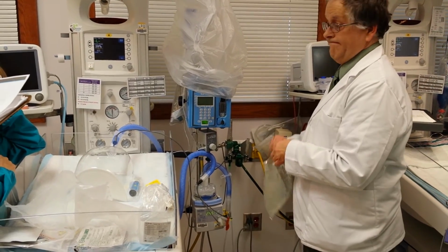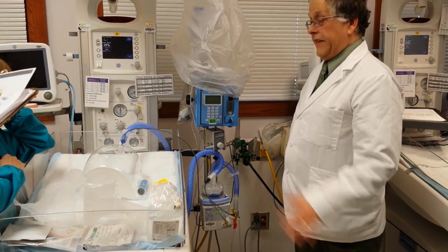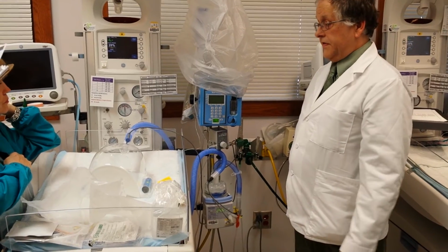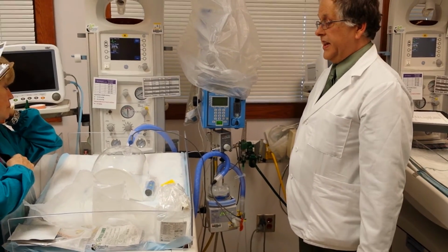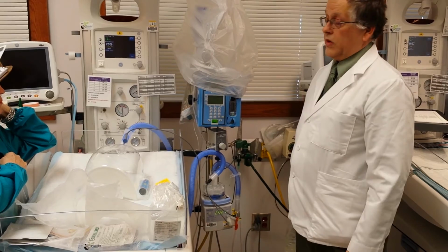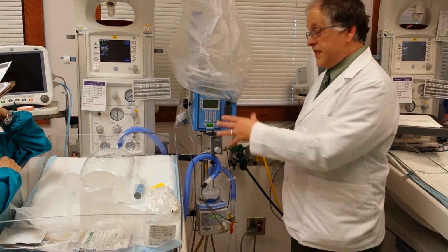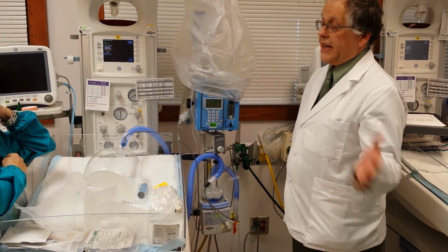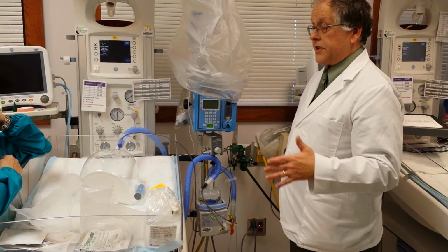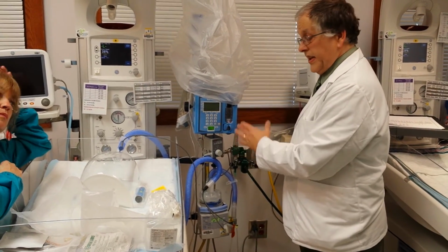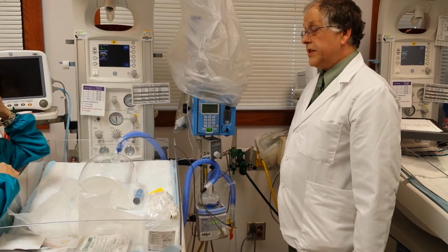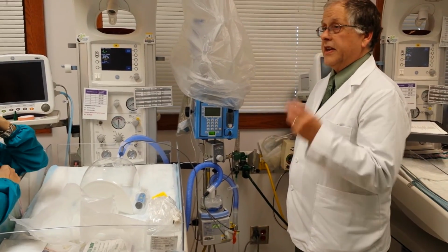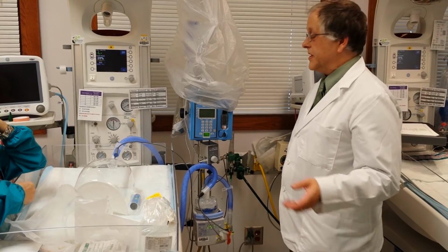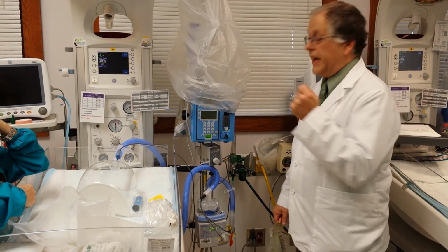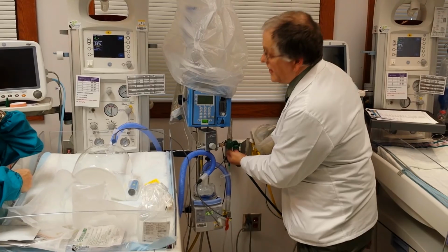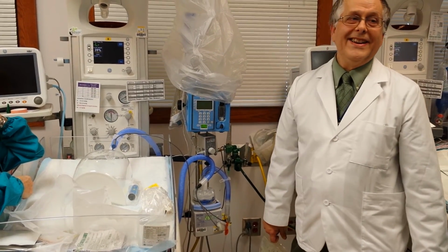And then, document. After you get everything up, it's good practice to verify your FiO2 just to see that it's what it should be. But with this setup, back in the old days, you really needed the analyzer so you knew what you had. With this Venturi, it's precise. If you set it up correctly, you know what it is.